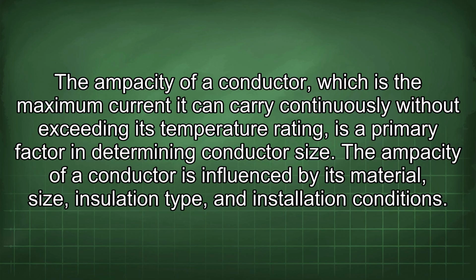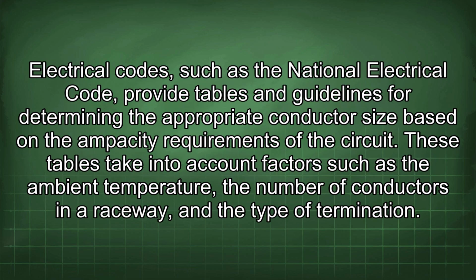The ampacity of a conductor, which is the maximum current it can carry continuously without exceeding its temperature rating, is a primary factor in determining conductor size. The ampacity of a conductor is influenced by its material, size, insulation type, and installation conditions. Electrical codes, such as the National Electrical Code, provide tables and guidelines for determining the appropriate conductor size based on the ampacity requirements of the circuit.